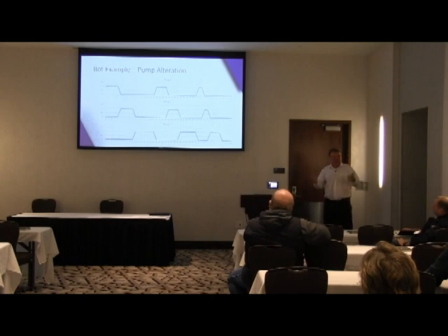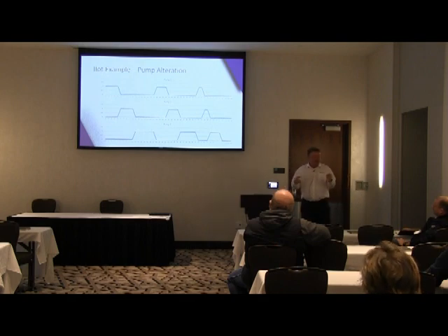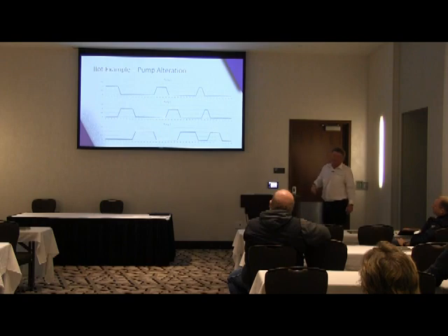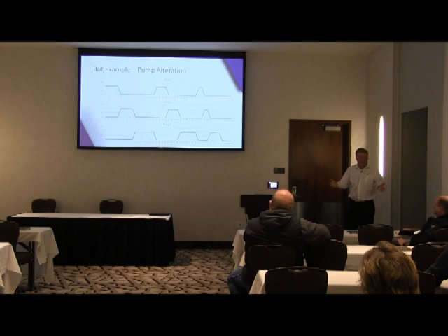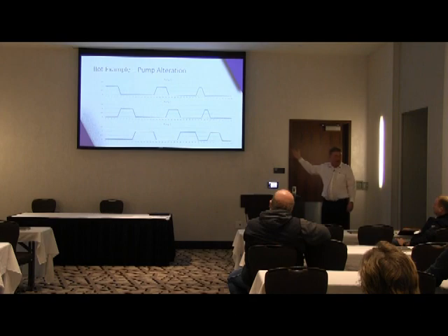It's hard to detect, but one of the models that they look at is that the amount of water coming in is varying, so you can't say this pump took 5 seconds, this one took 5 seconds, this one took 7 seconds, then three. There are no fast rules, but if you look at this over time, pump one is taking about 5 seconds, then 4 seconds. Pump one and pump two are acting semi-normally, but you compare pump three to them, and pump three is taking longer to do the same work. Now that I tell you that, if you just looked at this data, you'd have a hard time seeing it.